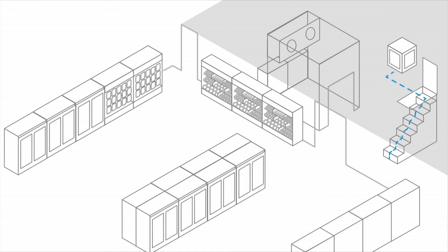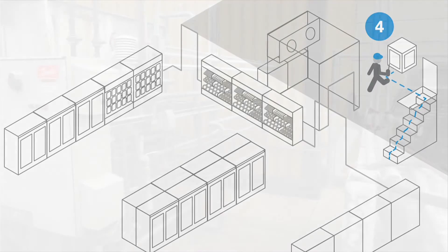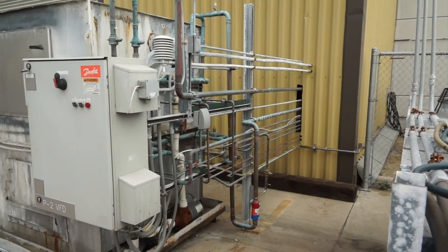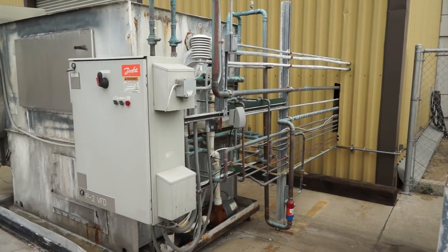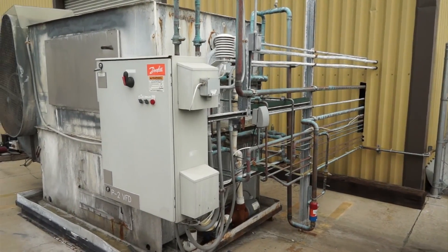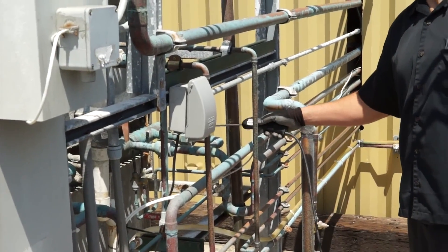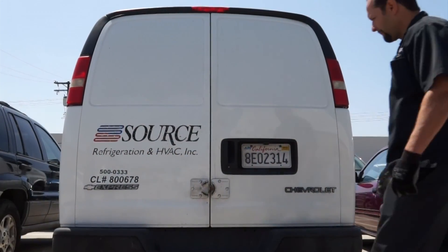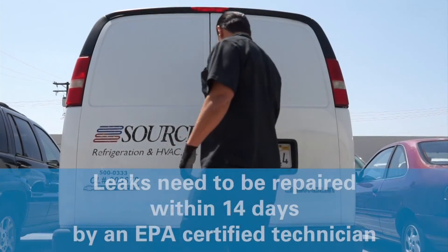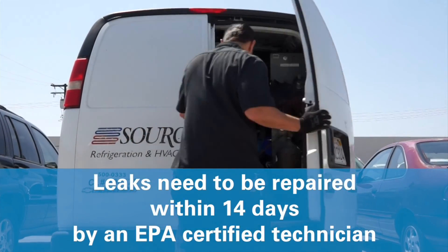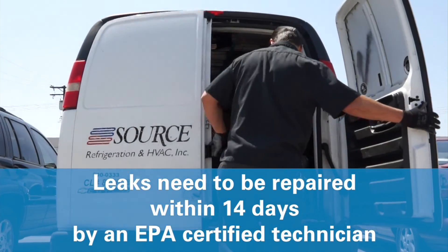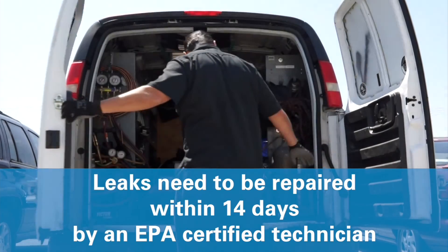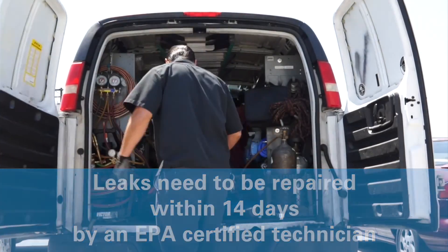Proceed to the rooftop condenser equipment. Make sure to look for oil stains and run the sniffer along the refrigeration lines. If any leaks are found, California law requires that they be repaired within 14 days by an EPA-certified technician.